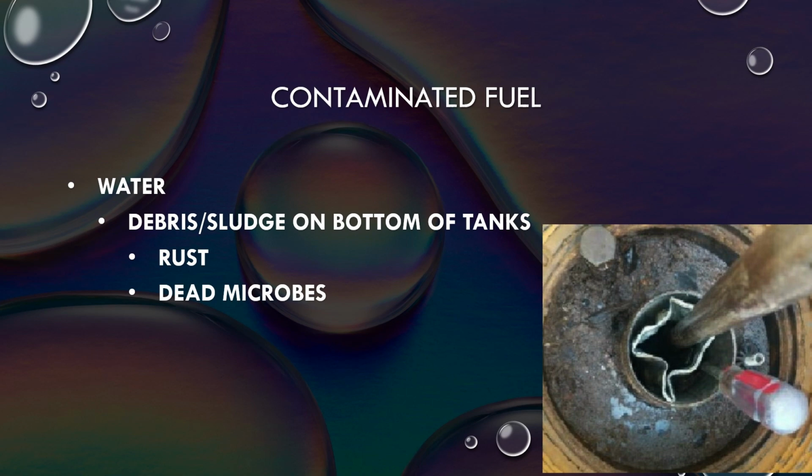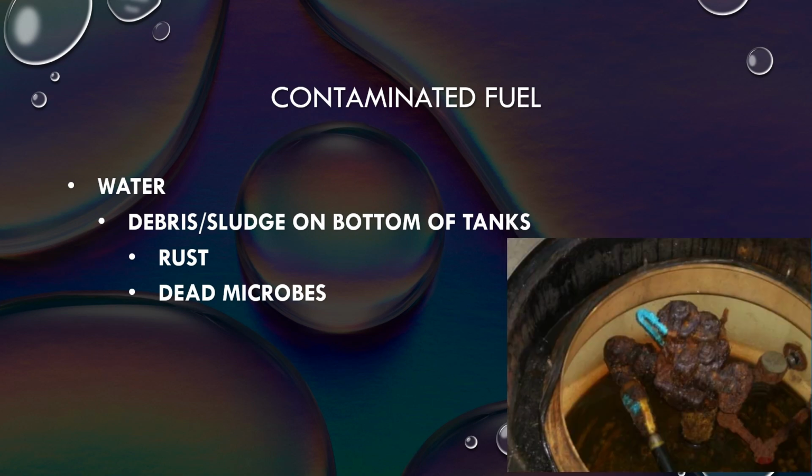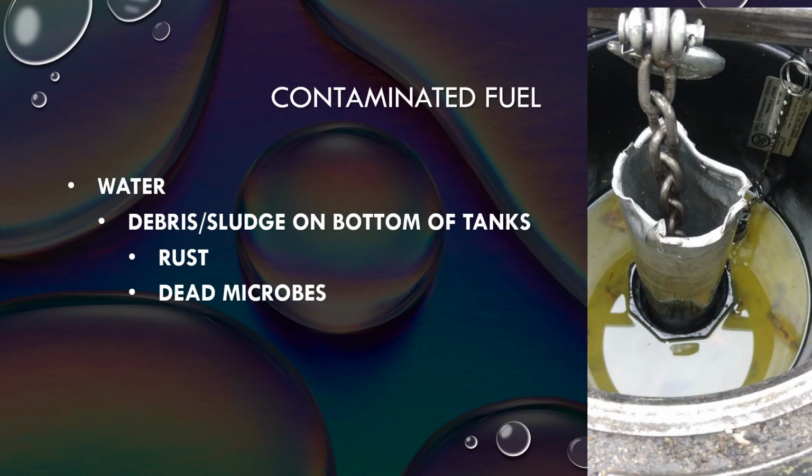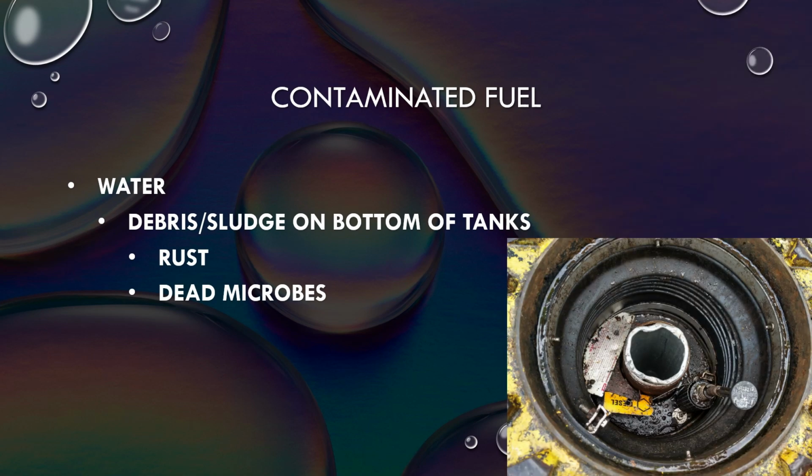So whenever a technician tries to pull those drop tubes out, they don't come out. So you can have symptoms of sludge, debris, and crud in the bottom of your tank show up as fake water alarms. So your floats get stuck on the probe, and whenever a water alarm goes into effect, you go out and you check your tank with a stick, and there is no water because it's the debris in your tank that's actually causing these water alarms. And you'll usually see them cycle. The alarms will go into effect whenever you get a delivery, and then they'll slowly go away.